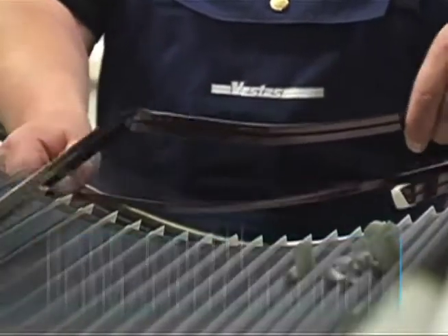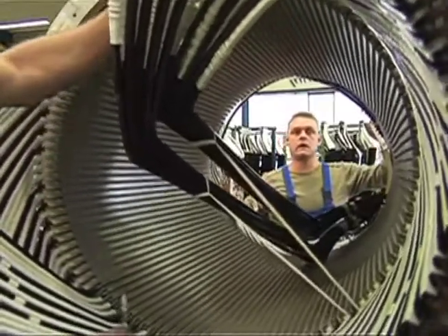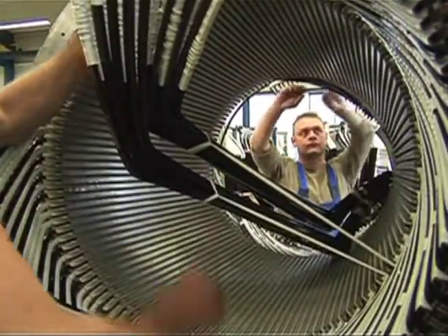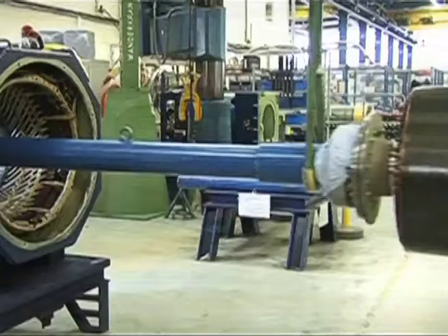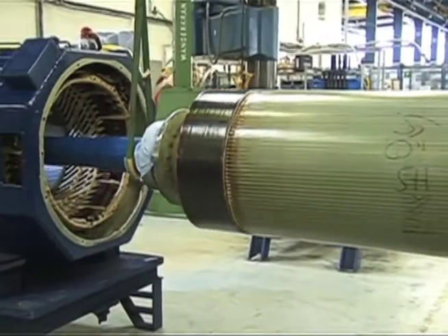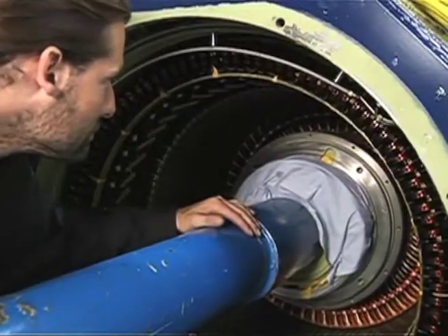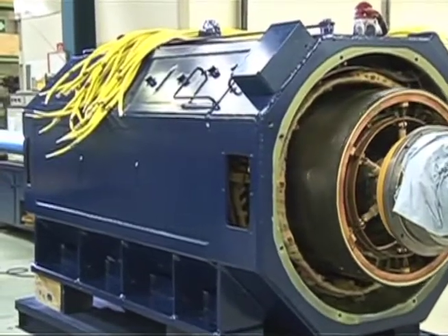Despite their scarcity in the United States, manufacturers research the use of these magnets because, unlike copper windings, their high energy density eliminates excess weight and size, reduces insulation degradation, shorting and electrical losses. However, with rare-earth permanent magnets, generators will require better cooling devices because the magnets cannot be exposed to high temperatures without permanent degradation of their strength.